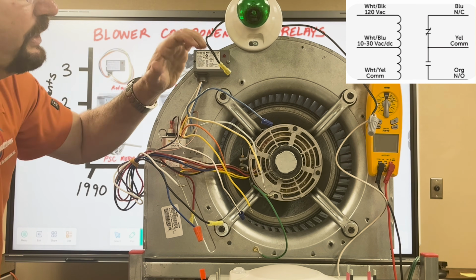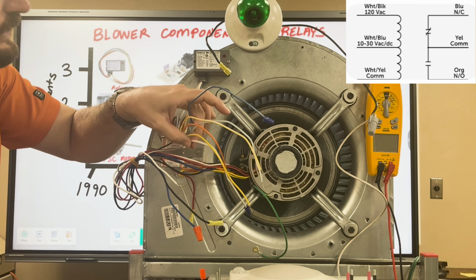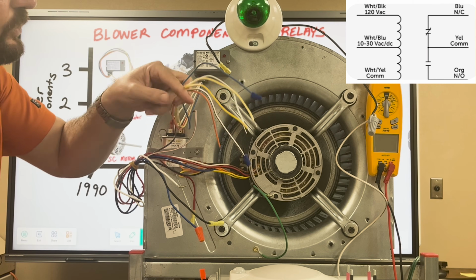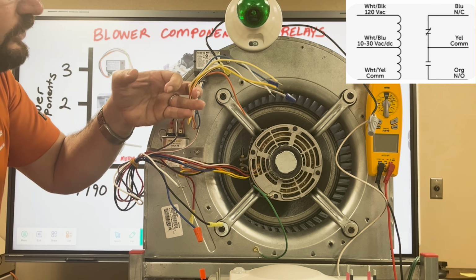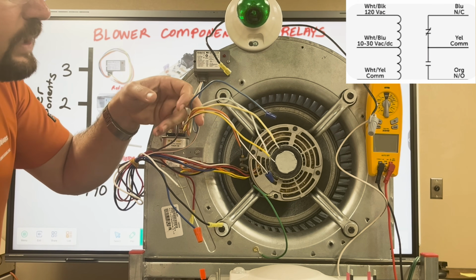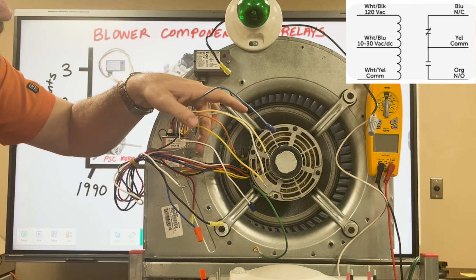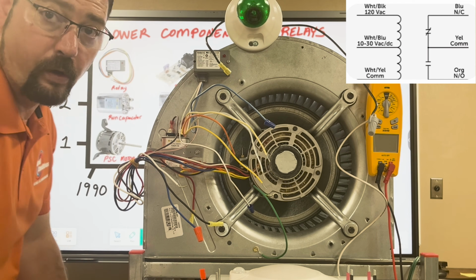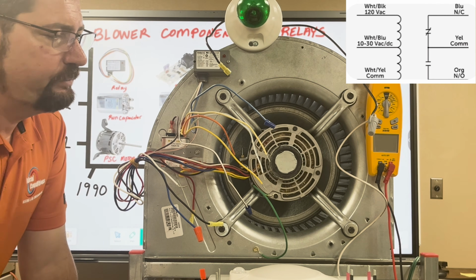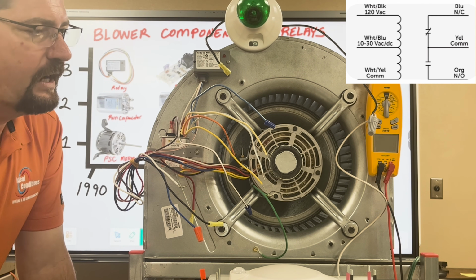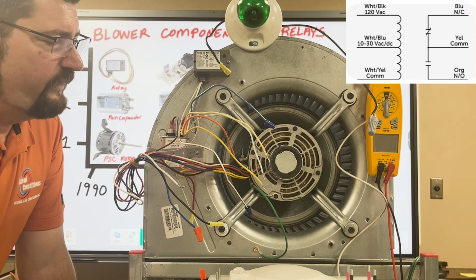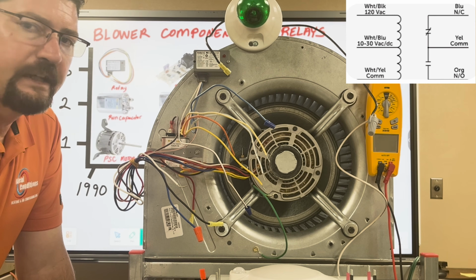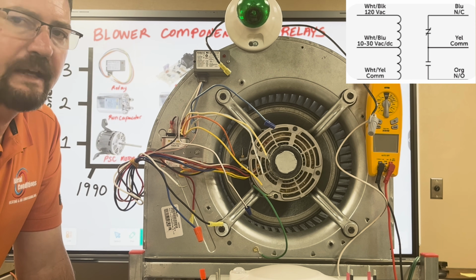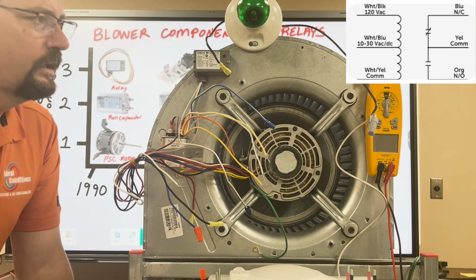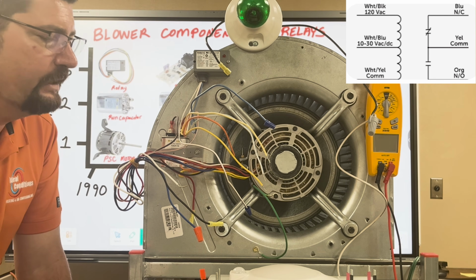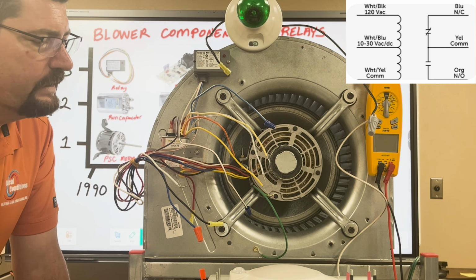So if you had to put a bunch of these in, as you can see, there are not your traditional terminals like you see on a relay. It's just a bunch of wires coming out of it. Some of them I have capped off because there are 6 of them and I'm only going to use about 4 in this application, maybe 5. However, if I wanted to see if I had coil voltage, I can just look for that one red light right here, which would be an indicator, and that's pretty neat. So we're going to get right into it.